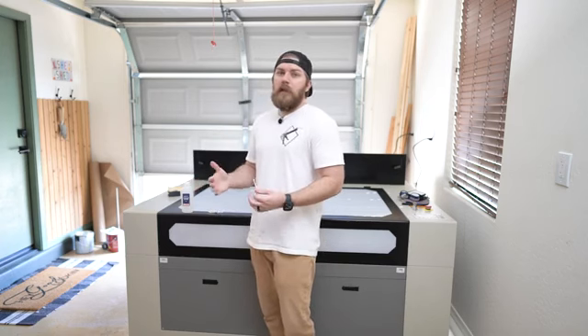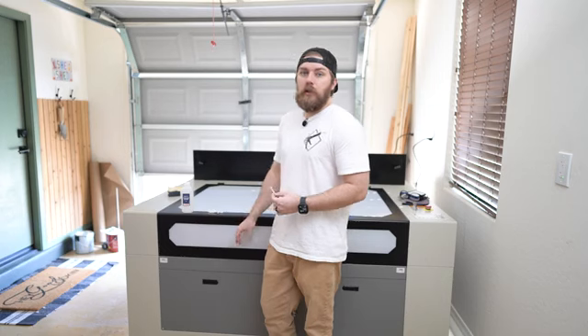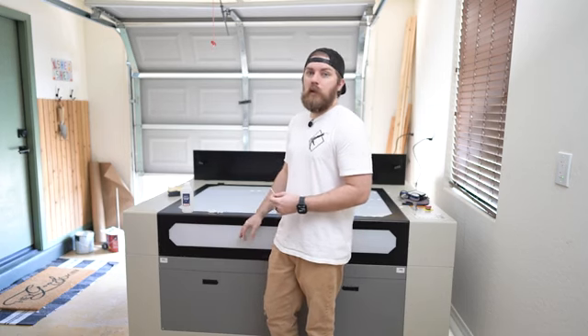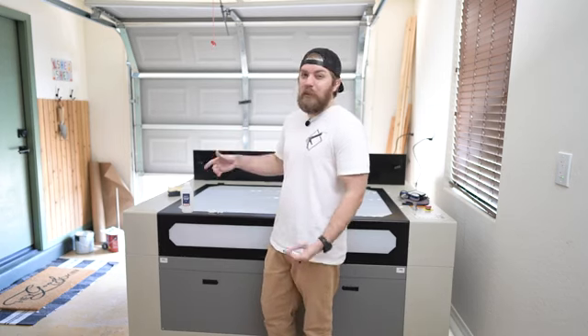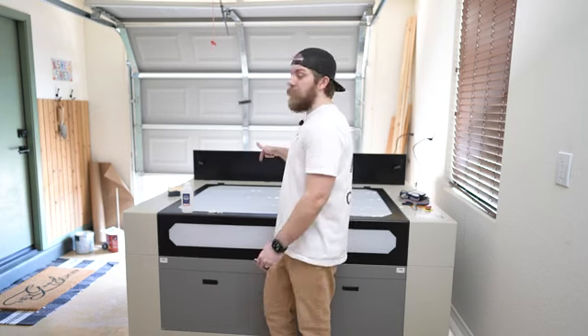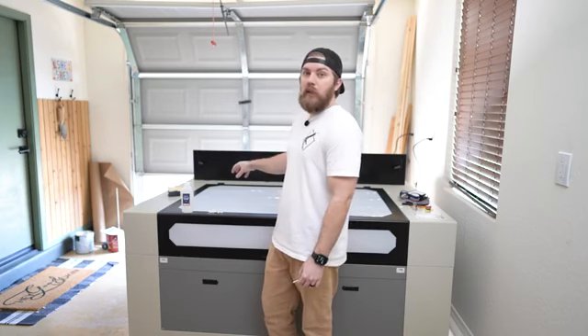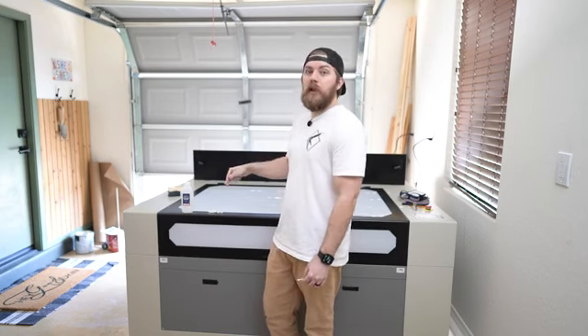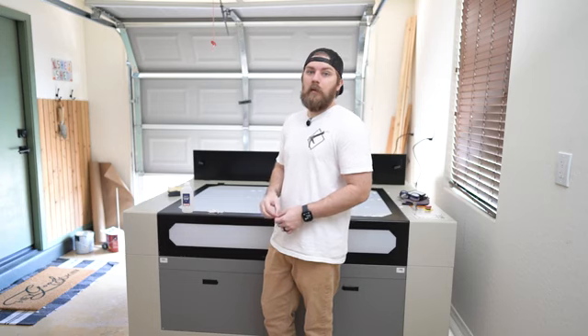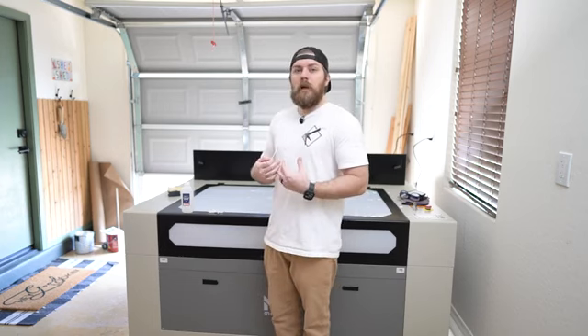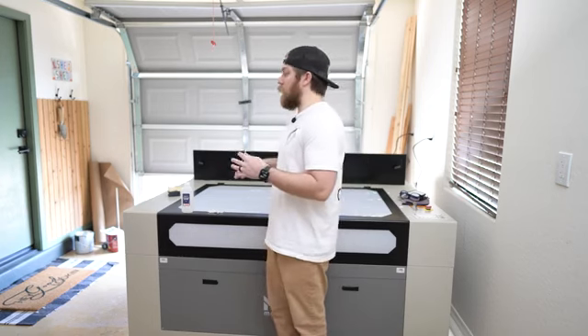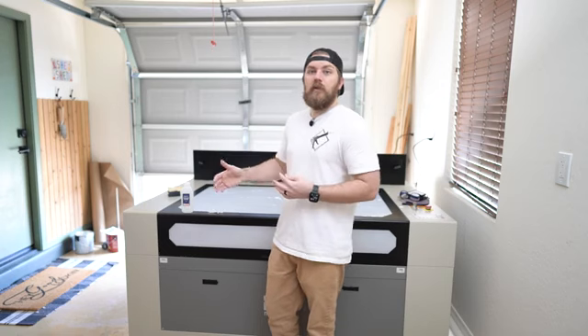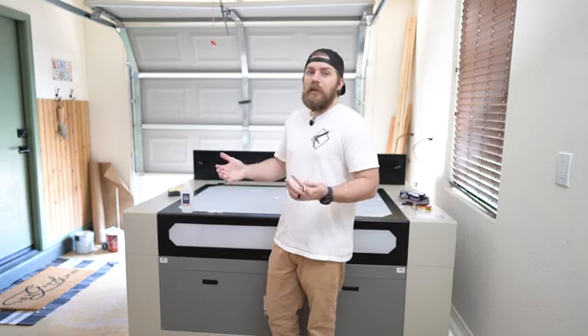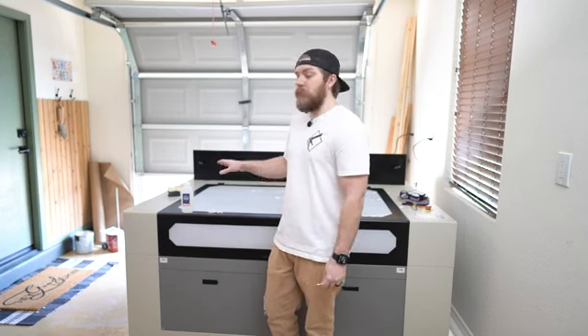Now, this may not be necessary, but a lot of these machines are gonna be run and tested before they're shipped out. So the back and side mirrors likely won't be too dirty, but the mirror attached to the laser head that directs the beam into the lens, that one will probably have some stuff on it. So just to make sure I'm doing my due diligence and making sure that there's nothing that's gonna skew the results as I dial this in, I think that's gonna give you your best shot. So that's what we're gonna do now.